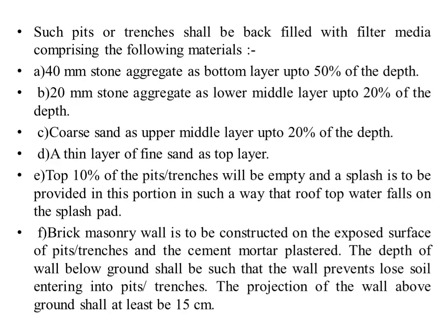Then such pits or trenches shall be backfilled with filter media comprising the following materials. One is 40 mm stone aggregate as the bottom layer up to 50% of the depth. Second is 20 mm stone aggregate as the lower middle layer up to 20% of the depth. Coarse sand as the upper middle layer up to 20% of the depth. A thin layer of fine sand as the top layer.